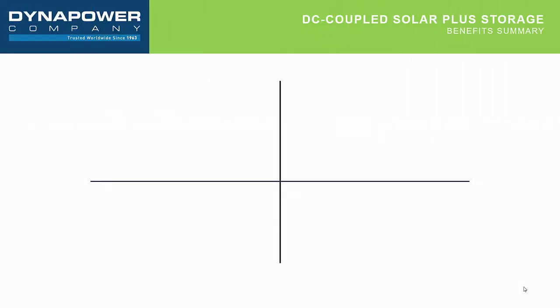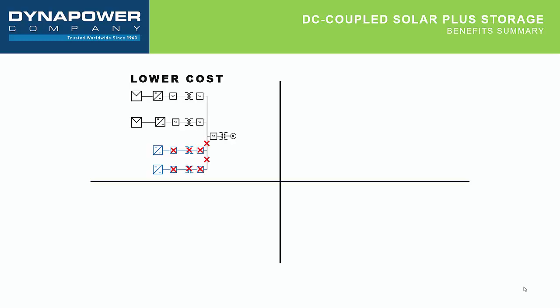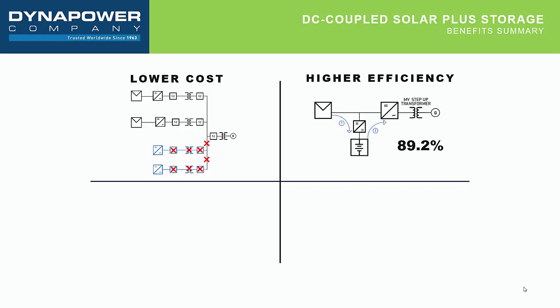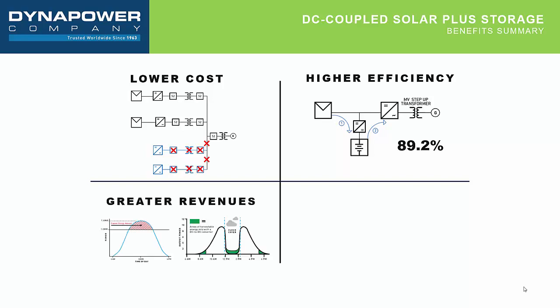Let's pause here and do a quick review of the benefits and reasons we're looking at DC coupled systems. We started with the lower cost. Removal of all the AC equipment improves the balance of plant costing overall. Higher efficiency translates directly to greater kilowatt hours in the lifetime of the system. And then we looked at some of the revenue side advantages as well: clipping recapture, low voltage harvest, as well as ramp rate control. And then of course there are the obvious tax advantages.